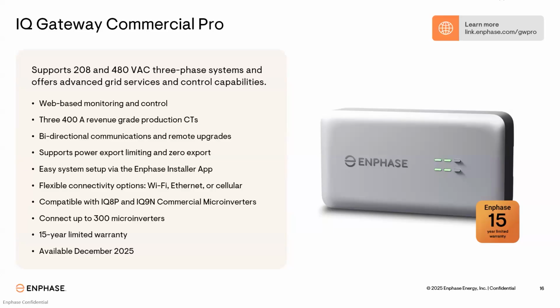It allows for bidirectional communication, which supports power export limiting and zero export. So if you are working at a utility that will only allow you to export a certain amount of kW, we can set that regardless of how large the site is, how much the production is. So you can build the system to fit the building's needs and limit that export. Or if your utility doesn't allow any export, we can set that to zero. Like in California, there's certain utilities that have to do with prevailing wage payments for labor when you export out into the grid. So we can greatly reduce those labor efforts with allowing and setting this up as zero export.